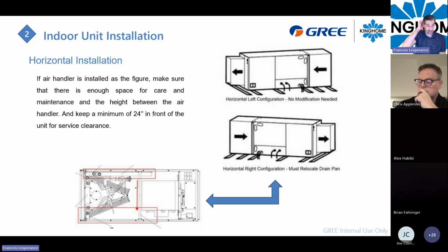This unit can be installed horizontally, in a left side or right side configuration. When you flip it to the left side, the secondary pan is already in the right spot, so you don't have to make any modification inside of the unit. But when you flip it to the right side, you will have to move the secondary pan to the other side. You will have to remove the coil right here and change the orientation of the secondary pan, and then you will have your right configuration.